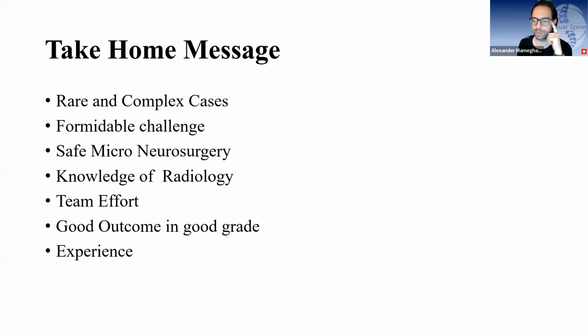There was a question: what setting do you use for the bipolar? Do you have some tips? Yes, I have some tips. I change the settings quite often. When I am at the muscle level, I use 30. When I enter the dura, the setting is 50, and on tumor, not more than 10. Not more than 10 on the cord. The mode is standard. I have fixed settings in my mind.